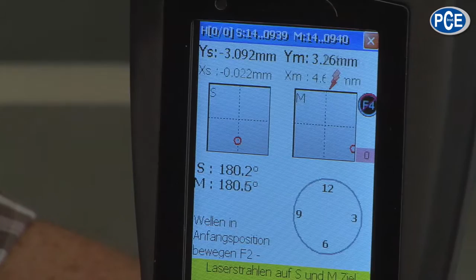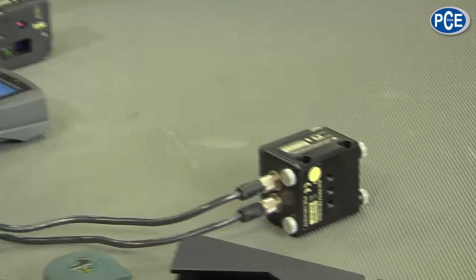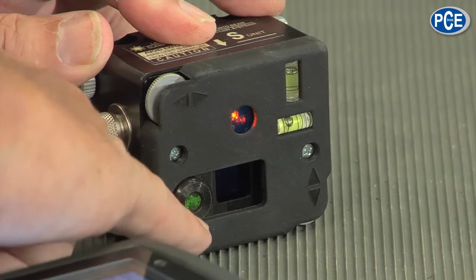On the PCE-TU 3 there are two laser sensors. A laser beam is sent from one sensor and received by the other, and the other sends the same back, received by the first. The received beam isn't just detected as present - there's a built-in position-sensitive photodiode, 10 by 10 millimeters in size, that sees exactly where the beam is received.